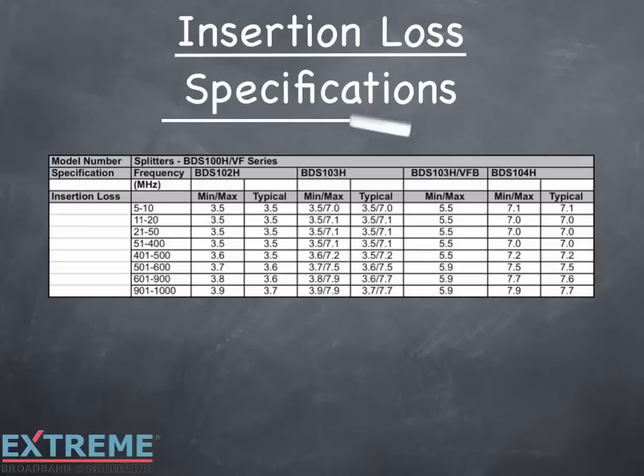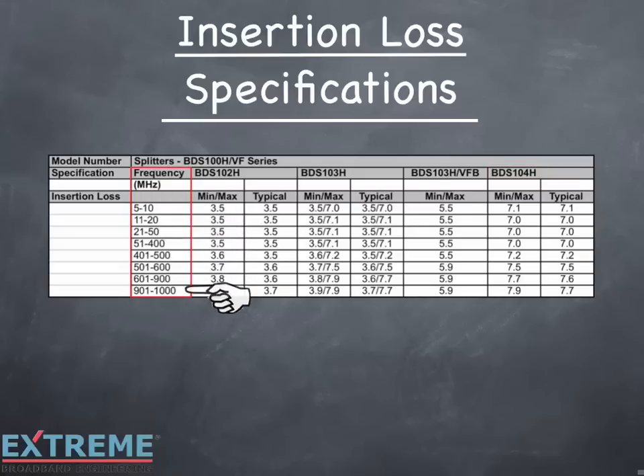Let's take a look at insertion loss specification sheets. Here we're showing a specification sheet for a broadband digital splitter series. This includes the two-way, three-way, three-way balanced, and four-way splitters. On the left side is the column labeled frequency. Here we break the frequencies into eight different bands, starting with five megahertz going up to one gigahertz. Next to that is the column labeled min-max — these are the worst case insertion loss numbers for these devices, normally used by engineers and designers of cable systems.